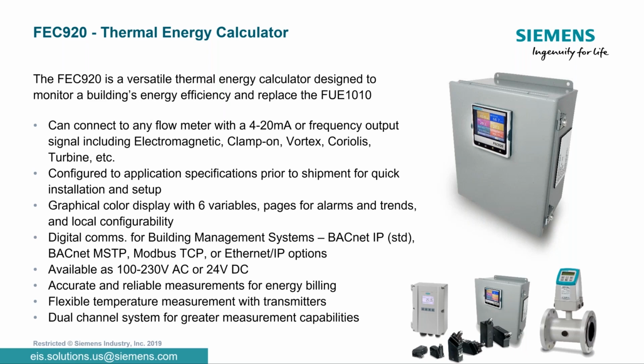This is a versatile thermal energy calculator that's designed to monitor a building's energy efficiency or for billing of your chilled water and hot water. What's nice with this design is it's a package solution from Siemens EIS that can be ordered through Lesman. We can connect to any flow meter. So if you've got a flow meter that's out there, whether it's a Siemens product or another manufacturer that has a 4 to 20 milliamp or frequency output for the flow, this device will take that flow input.